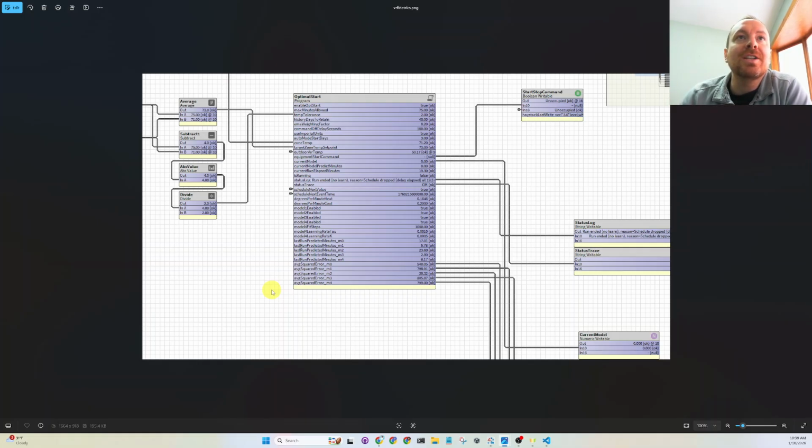So traditionally in optimal start, they've only been doing a simple degree per minute model. Linear model is what the paper calls it. We've talked about this in the very first YouTube videos. This is model 0 essentially. And then we get into these more elaborate math models here. And I decided originally I was not going to do this model 3 and 4 because it was just getting kind of complicated. Now it's really complicated, but it appears to be working.